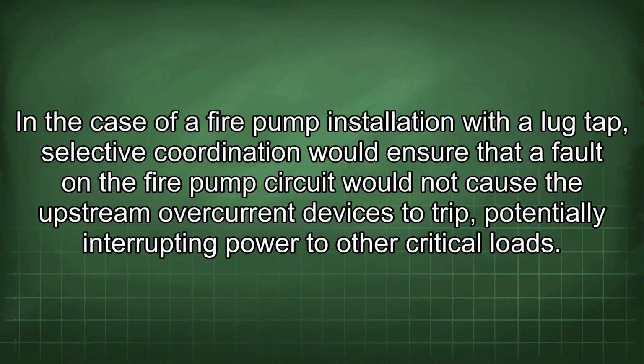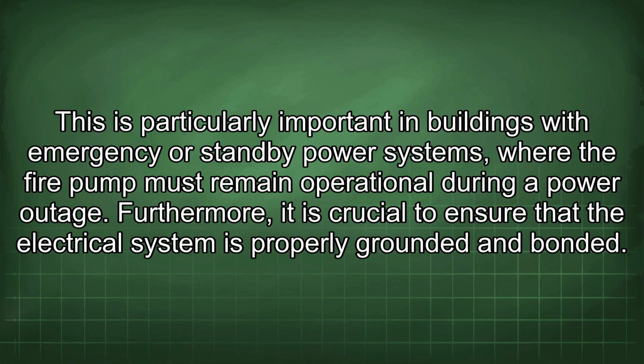In the case of a fire pump installation with a lug tap, selective coordination would ensure that a fault on the fire pump circuit would not cause the upstream overcurrent devices to trip, potentially interrupting power to other critical loads. This is particularly important in buildings with emergency or standby power systems, where the fire pump must remain operational during a power outage. Furthermore, it is crucial to ensure that the electrical system is properly grounded and bonded.